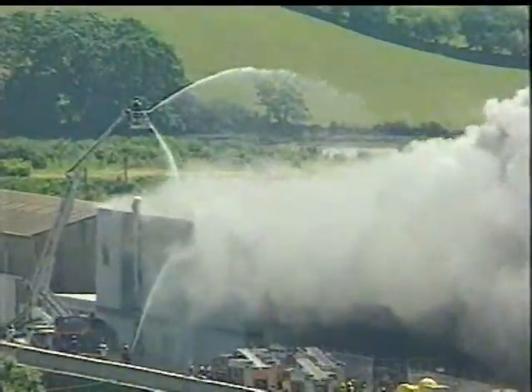If a fire develops in a building constructed with foam-cored composite panels, there is a risk that the panel cores can become involved in the fire, leading to possible collapse of the panel systems and an acceleration of the rate of fire spread. We can't get to that foam because the outside is protected against weather, and the inside is protected because they keep a sterile environment for food production. It burns up through that sandwich and right across the building. We just can't get to it.